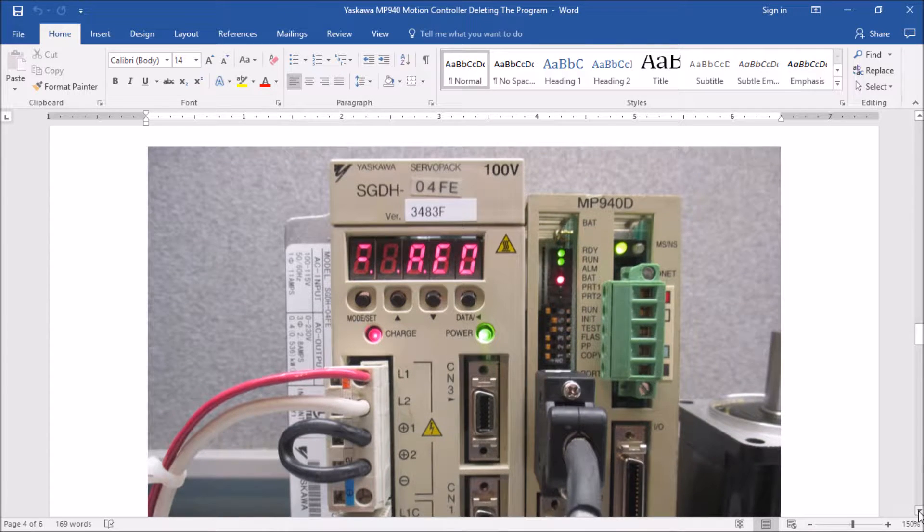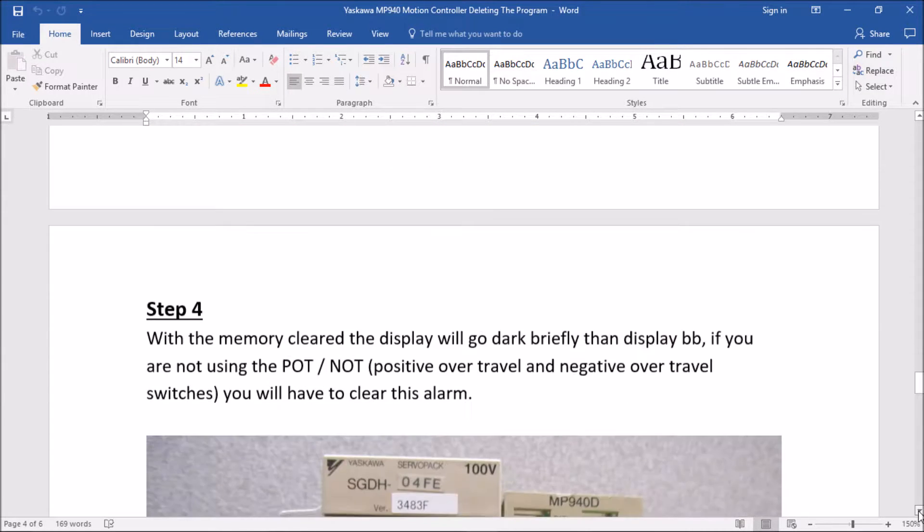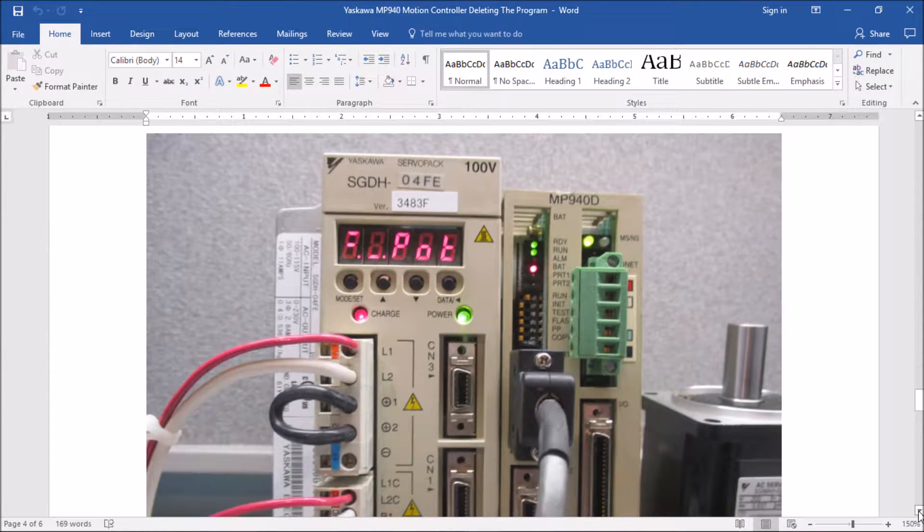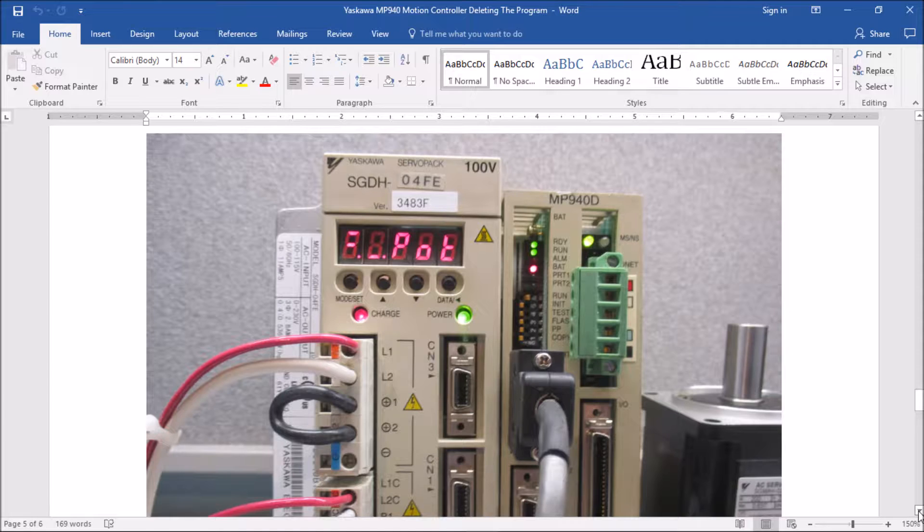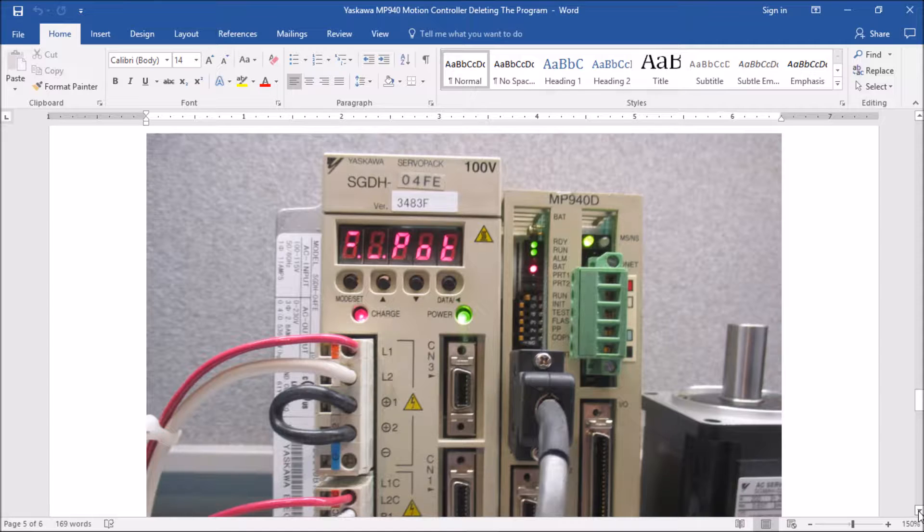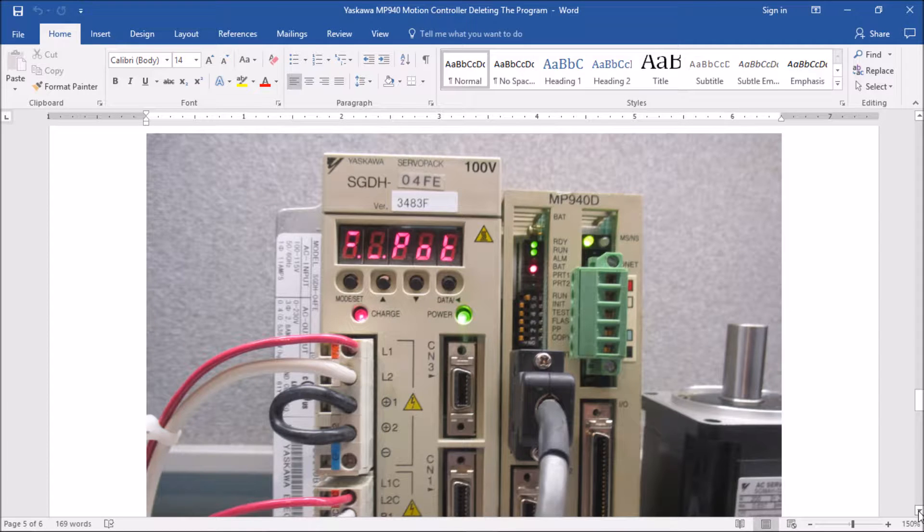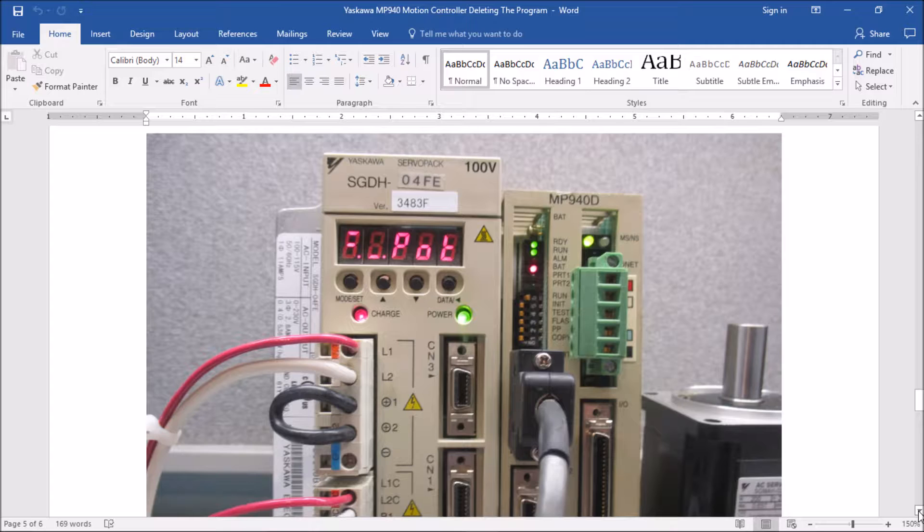Now I'm going to scroll down here a little bit further on down to step four. Here in step four I'm going to power cycle the amplifier. And once it powers back up I will briefly flash into BB for a few seconds, and then I will have a pot not alarm, but you may also be into BB or into run mode. But for me I'm in pot not because I am not using the positive over travel or negative over travel limit switches. So that's why I have this alarm because it is not seeing them switches active. And to clear these is another step that I have in another video on how to mask the pot not alarms.